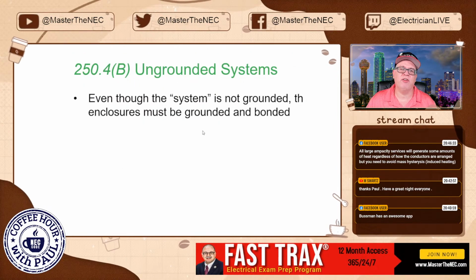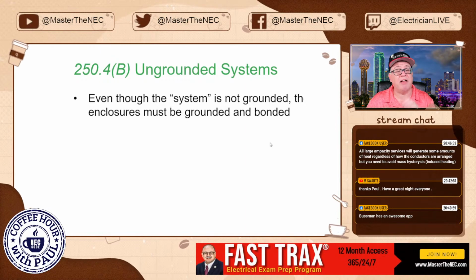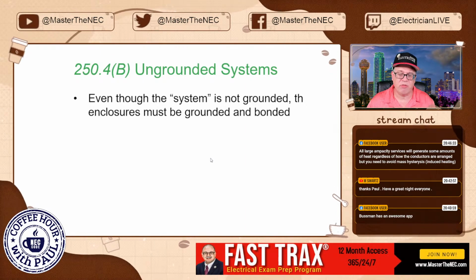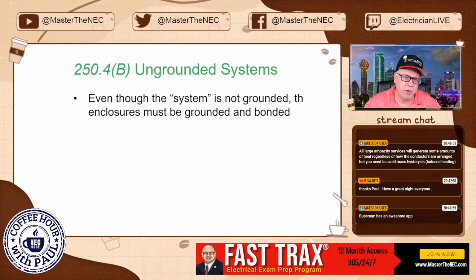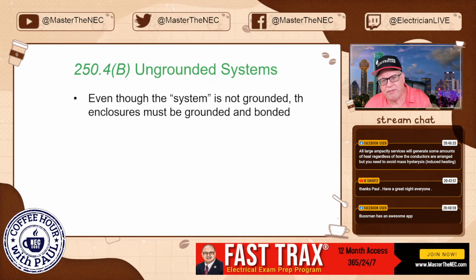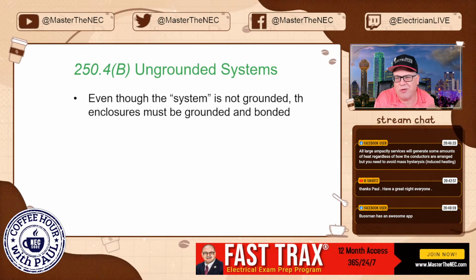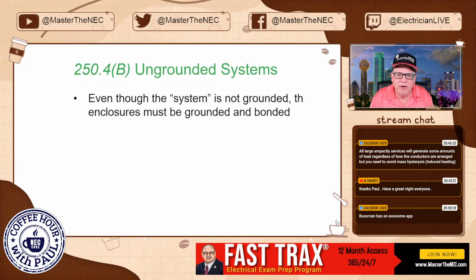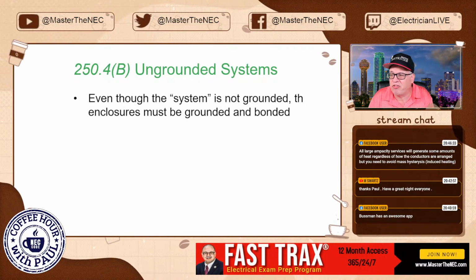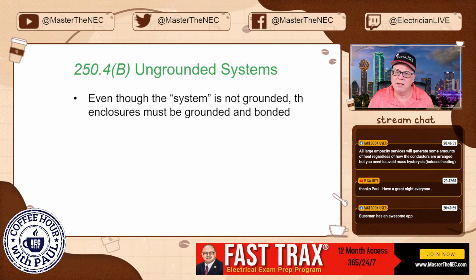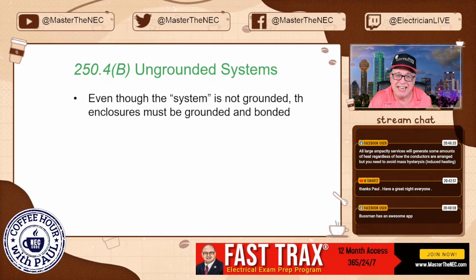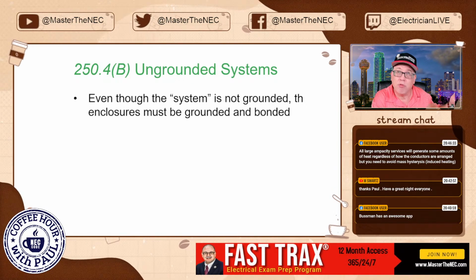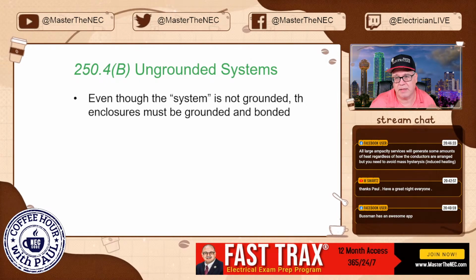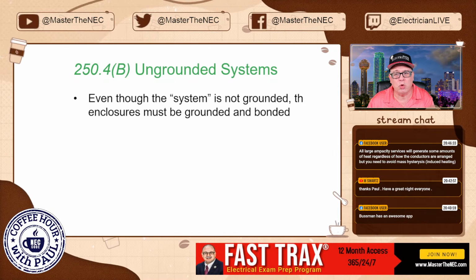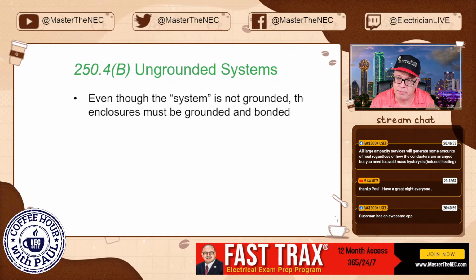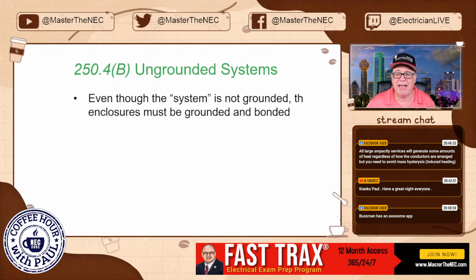All right, ungrounded systems, 250.4(B): even though the system is not grounded, the enclosure must be grounded and bonded. So what does that mean? Just because we're generating an ungrounded system means we're not taking one of the phases and connecting it to earth, we're not making that intentional connection to earth. That's not going to remove us from doing things like grounding and bonding because we're still going to have overcurrent devices we have to clear, right? So we're just not establishing an intentionally connected to earth system, a grounded system. We're creating what's called an ungrounded system, okay? But we still got to remember, we've got bonding rules, we got grounding rules, we got breakers we still got to trip, things like that. So keeping all that in mind.